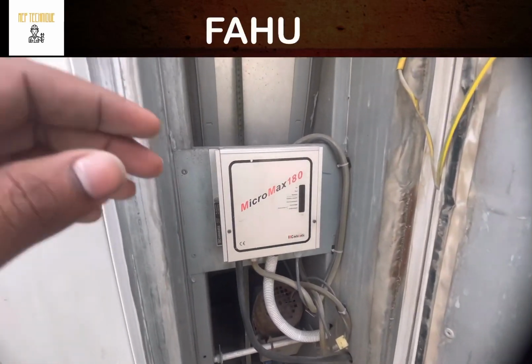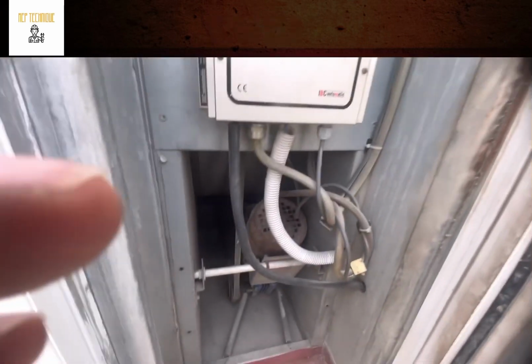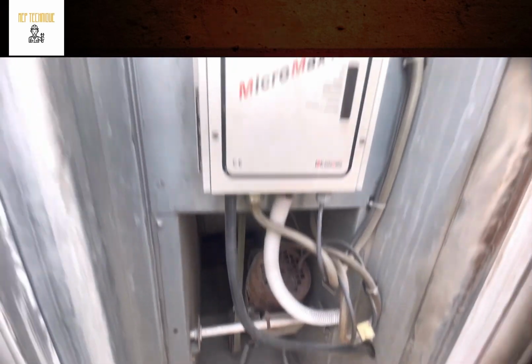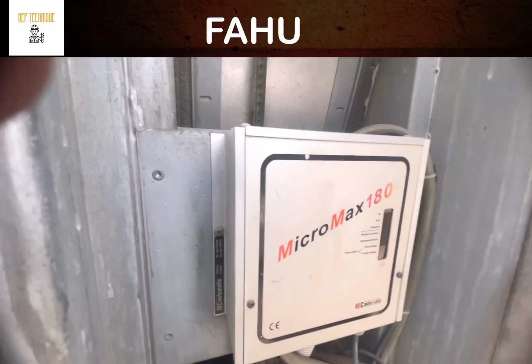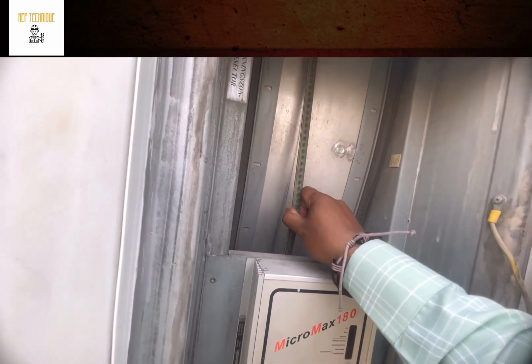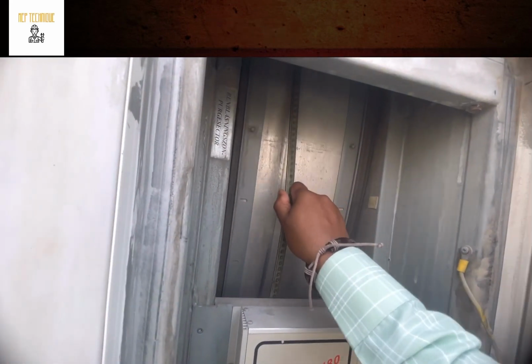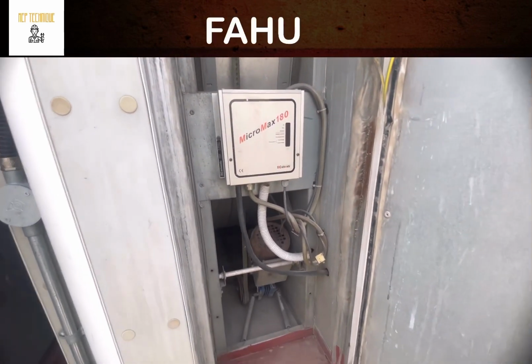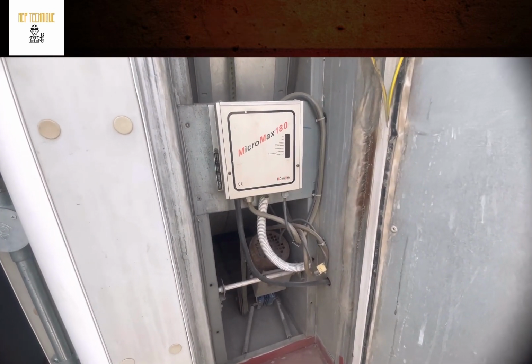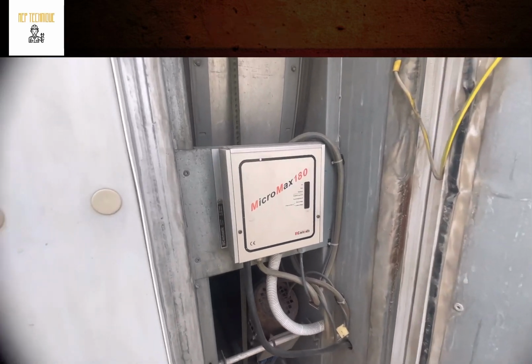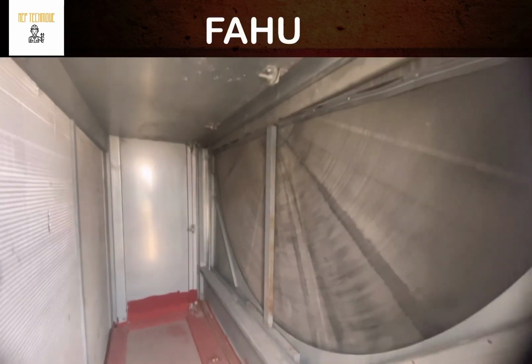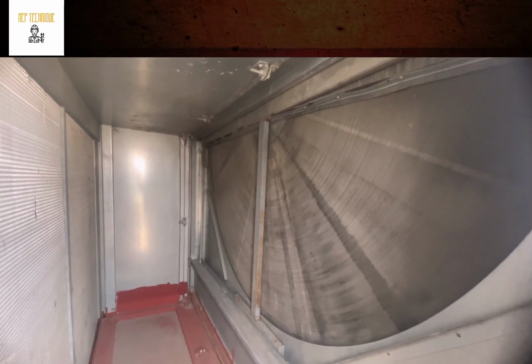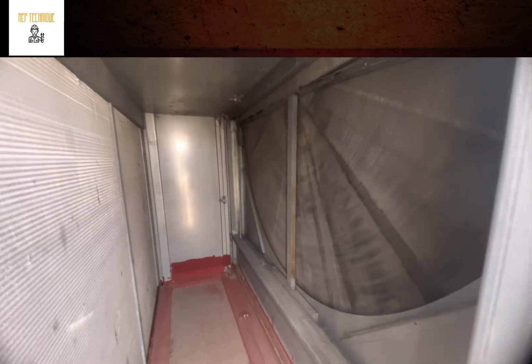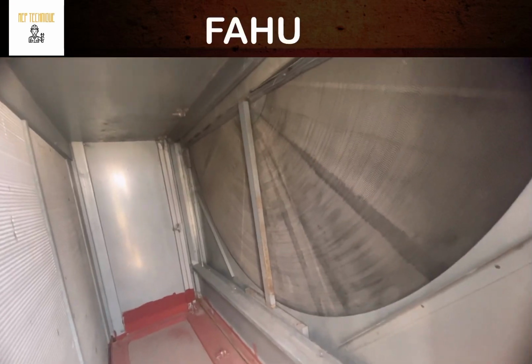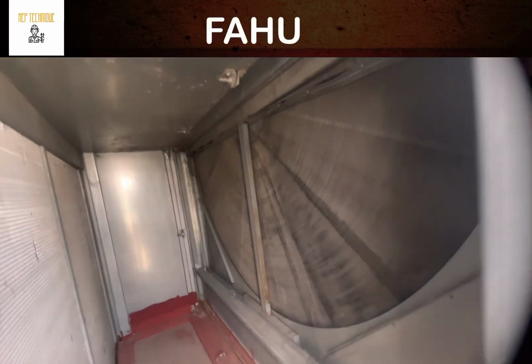After the filter section, we'll move to the heat recovery wheel. So this is the heat recovery wheel, you can see. This is the controlling system, and this is a small motor which is controlled by this control center. The heat recovery wheel is made with high conductivity material with a honeycomb structure. The main purpose of the heat recovery wheel is to recover the heat, that means energy, from the exhaust air. You can see here, there's a big wheel. It will affect the sensible heat and latent heat, that means it will affect the temperature as well as humidity.